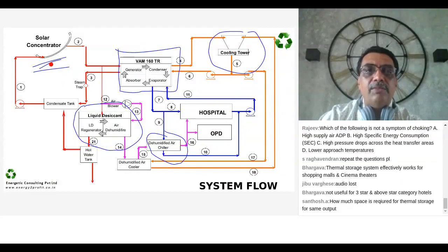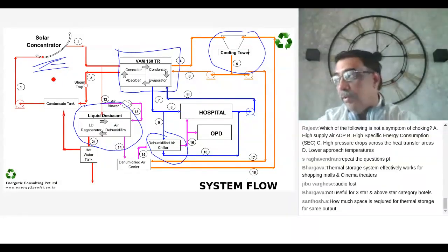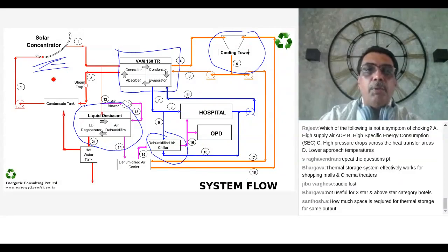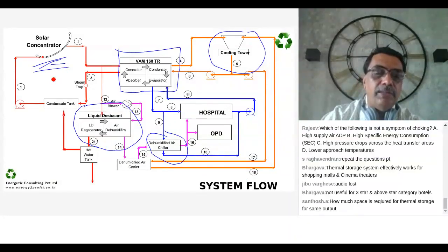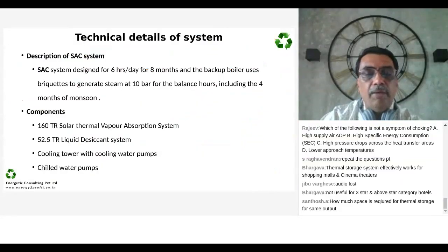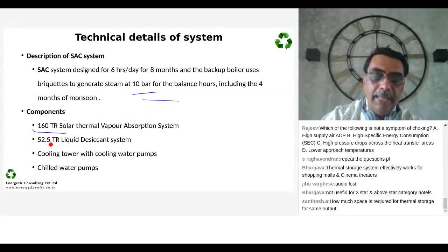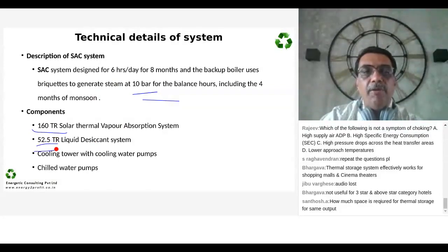Now during the hours when solar energy is not available, night hours and morning hours, a backup was provided with a steam boiler which operates with renewable energy, which is 100% renewable. So there's no conventional fuel. The conventional fuel was completely replaced. Solar air conditioning system for 6 hours, 8 months, and the backup briquette fired boiler for the rest of the period. 160 TR was the air conditioning system. 52.5 TR was the liquid desiccant system. Significant large number.